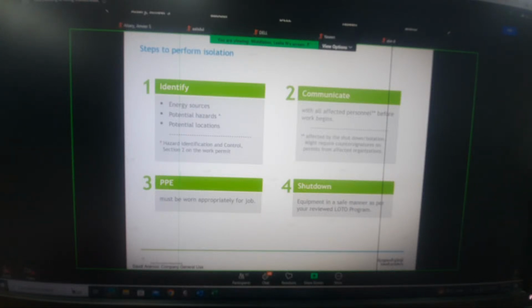Prepare for the isolation by identifying the types of energy and all potential hazards generated by using the equipment information, procedures, and hazard identification when developing the specific work permits. Identify what needs to be locked or controlled by locating all hazardous energy sources. Communicate with all affected personnel. Tell affected employees about the lockout and why you have to do it. Additionally, further controls may include counter-signatures on permits from affected organisations as required.